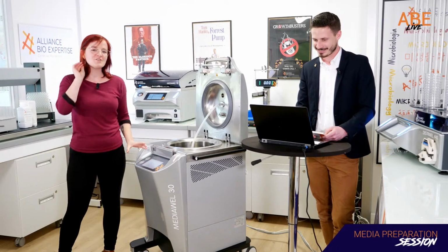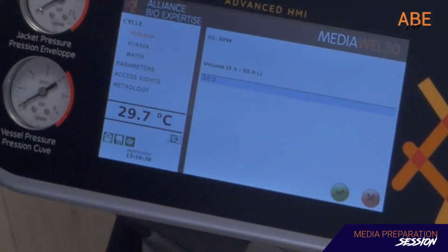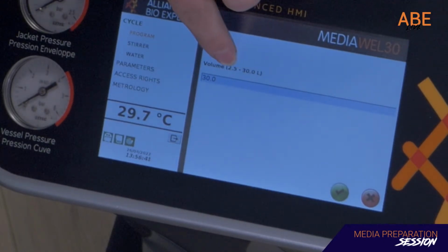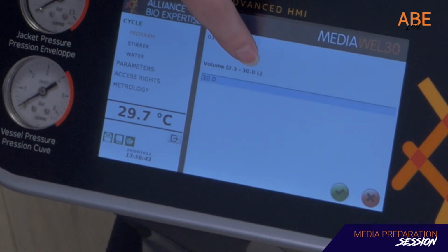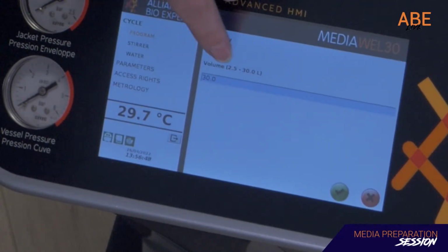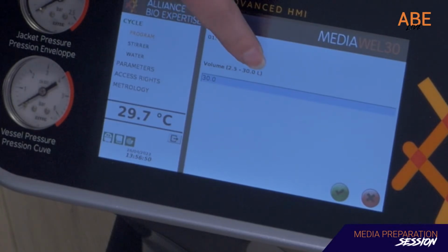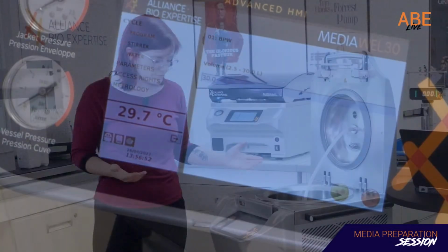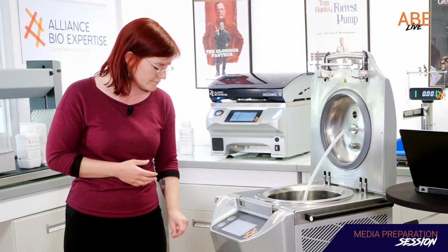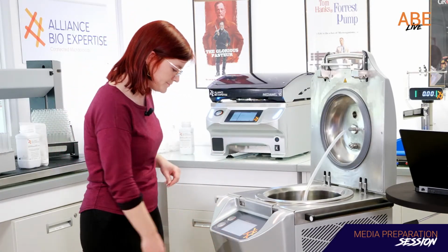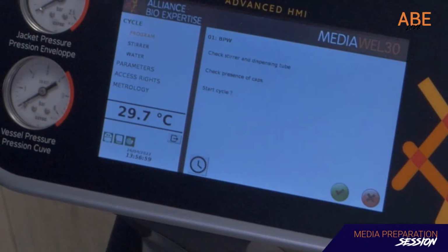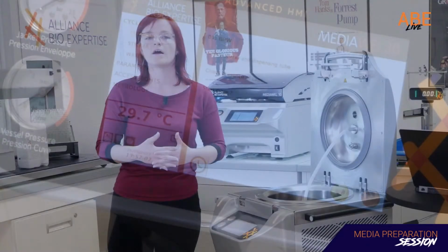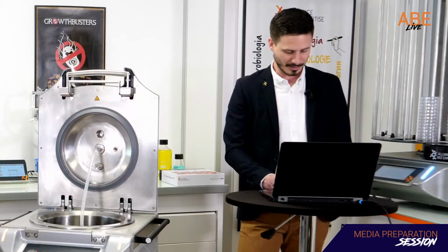The next question the MEDIAWEL asks you is the volume you are going to prepare at that cycle. So you see here, you always have values, the minimum and the maximum range that will regulate the values in the field. So here it's telling you that you can do minimum 2.5 and maximum 30 liters. So let's say we go for 30. And it is done. From here, the only thing I need to do is to press on the green tick and the cycle will start automatically. Okay, quick and easy.